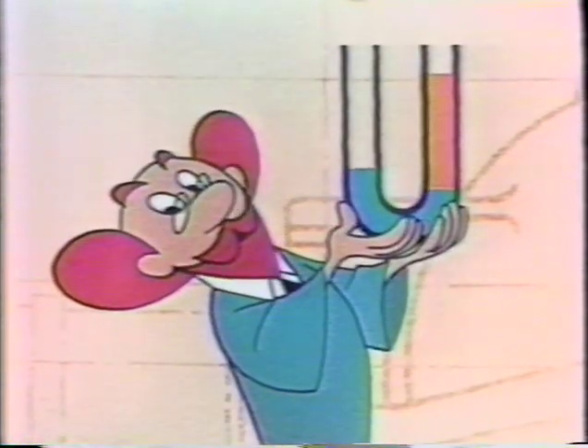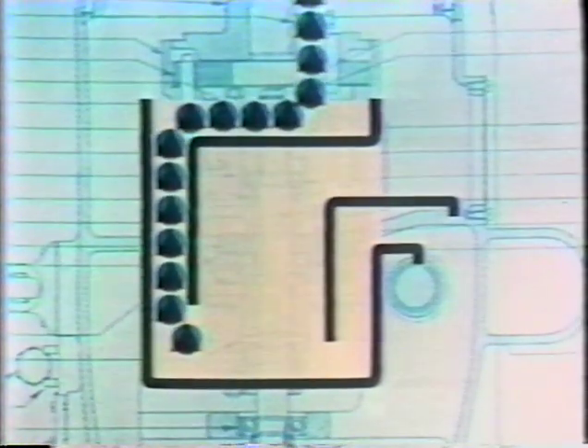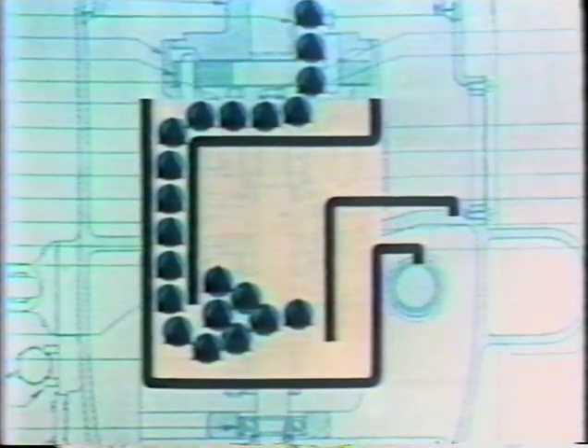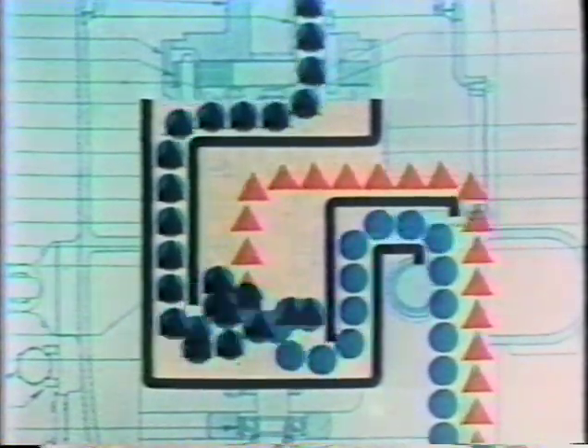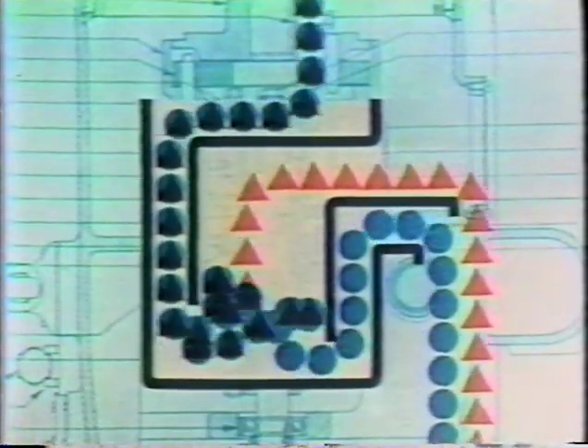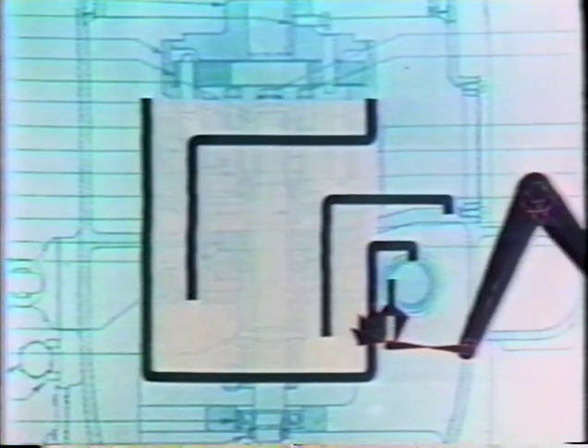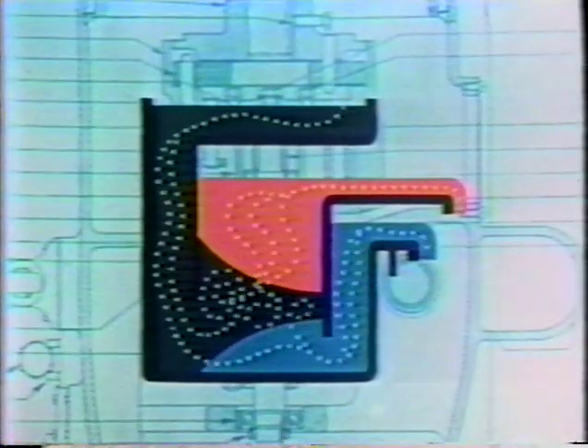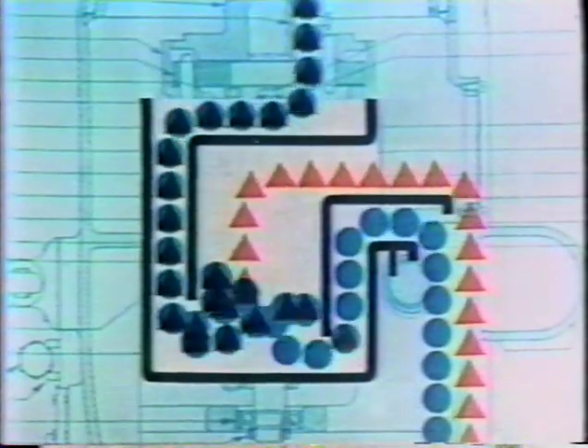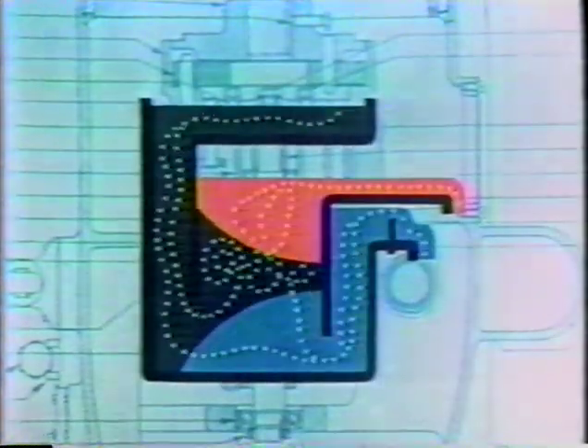What we have to do now is to make the tank more practical at the outlets and the inlet. The feed material is fed continuously through the inlet passage, after which it passes under the first baffle and on into the tank, where it forms a neutral zone. The light phase then rises to the top outlet, and the heavy phase sinks towards the bottom and is discharged through the lower outlet. To make the tank adjustable for different immiscible liquids, we can provide the lower outlet with a so-called dam. If the dam is set low, the position of the neutral zone becomes low too, risking some of the light phase escaping with the heavy phase. And if we set the dam high, we obtain precisely the opposite result.